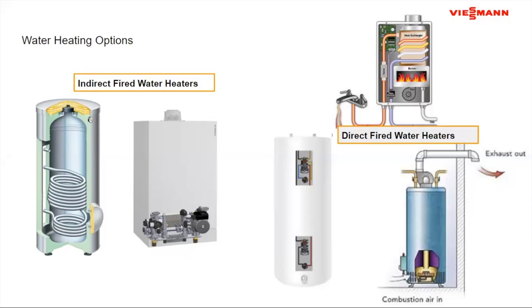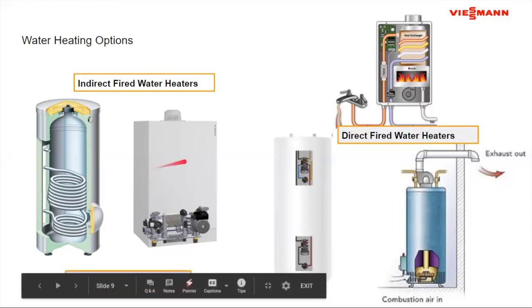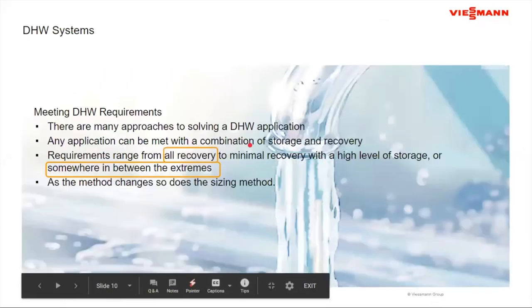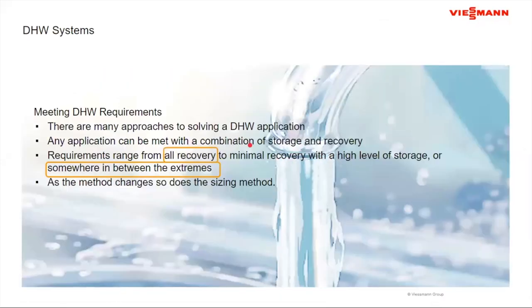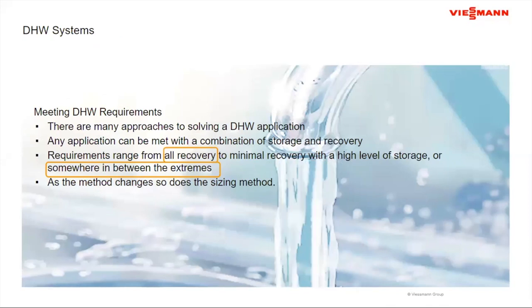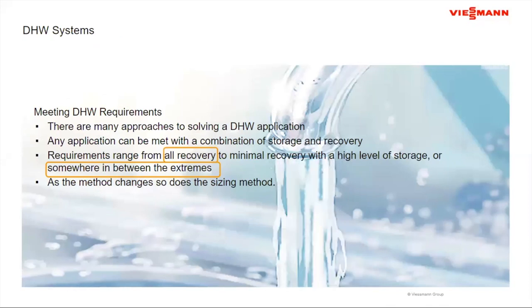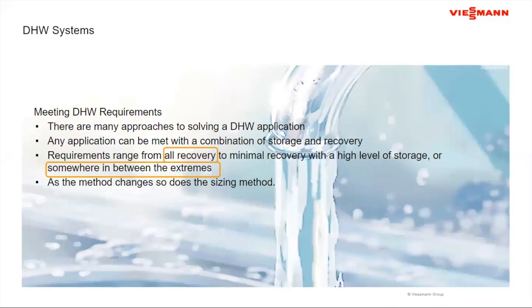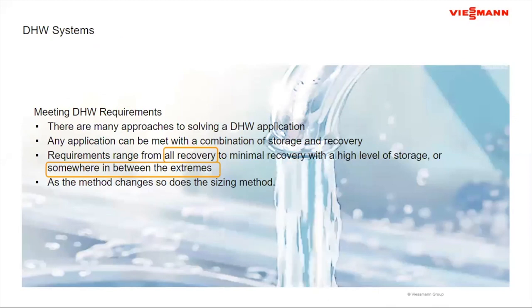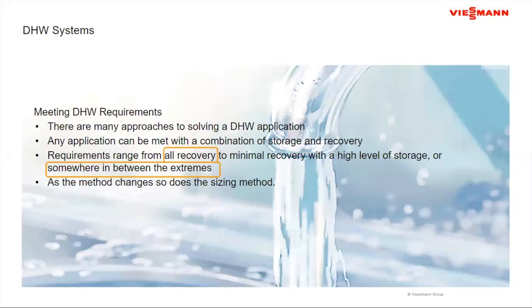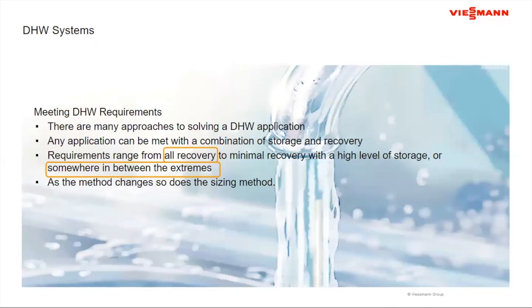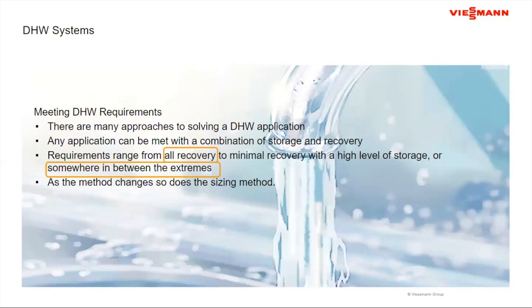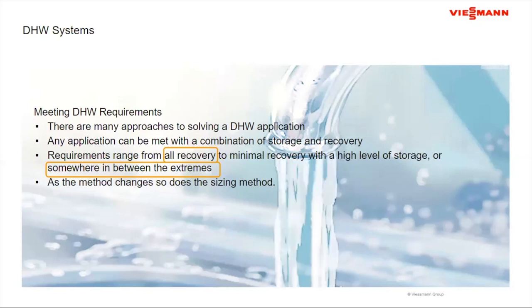For our discussion, we're going to go to the indirect fired method because in this building, we are going to have a heating boiler that we can couple it with. Now, when we start to do domestic hot water, although both methodologies of a combi boiler and a tank style indirect are connected to a boiler, there's a lot different methodology in looking at the application of these, and particularly the sizing. So when we look at domestic hot water, when we look at providing for the building, the approaches always come down to two things, recovery and storage.